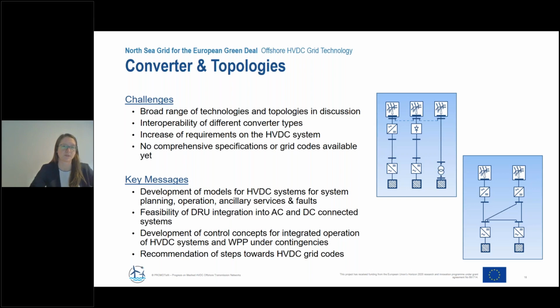And from this it was concluded that the diode rectifier integration, the grid forming controls were already given from the previous work, that the diode rectifiers can be integrated into AC and DC connected offshore systems, and thereby also testing the interoperability of the different controls. So for example, voltage source converters with offshore grid forming and grid following wind parks, and seeing that it's also possible to have a smooth changeover from the different control modes.